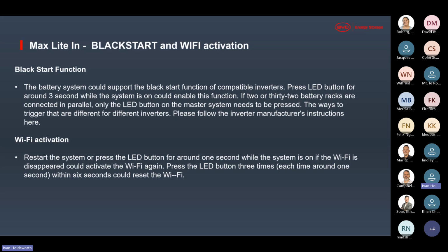Supposing you're installing an inverter that needs to black start, or you're installing somewhere at night where there's no grid or anything like that, and you'd like to power the inverter for the purpose of commissioning, you can hold the LED button for 3 seconds. The LED will flash briefly, and it'll give power out on its battery outputs. Please make sure you check your polarity and all your DC connections are correct before doing a black start.